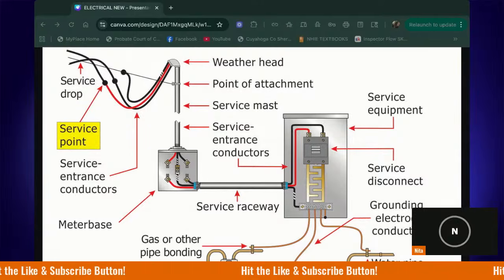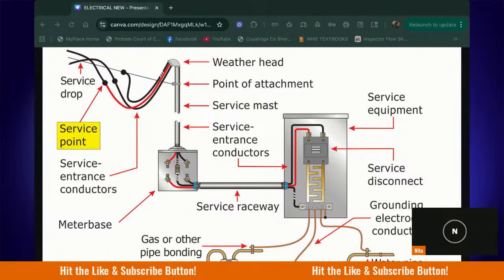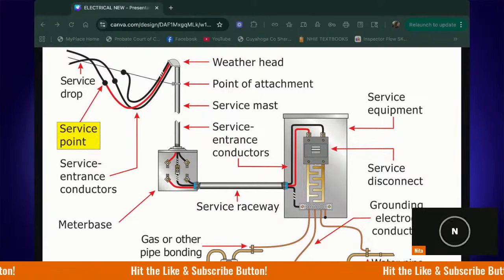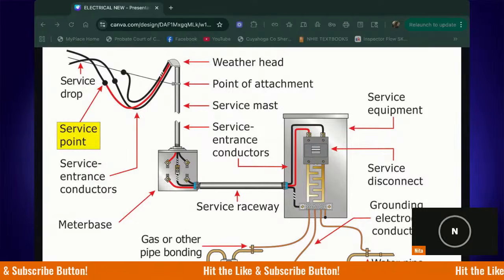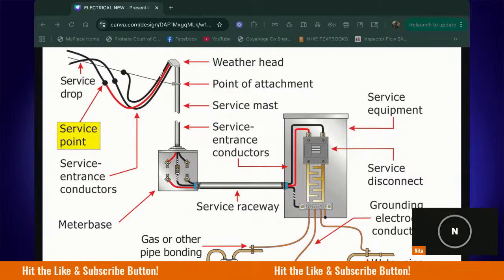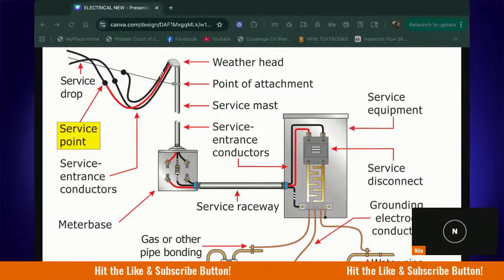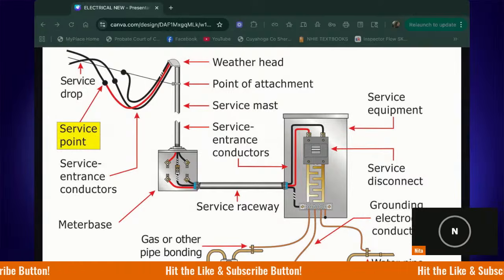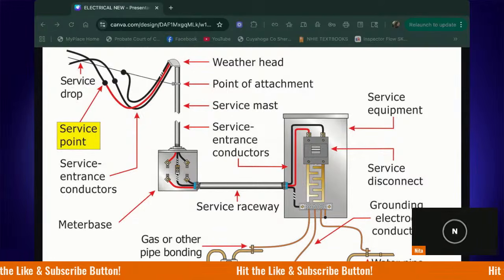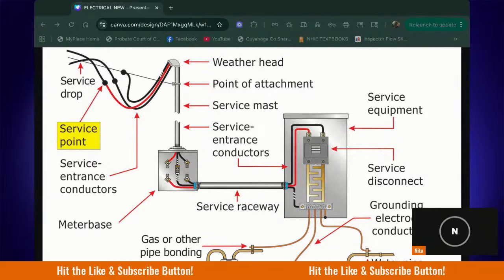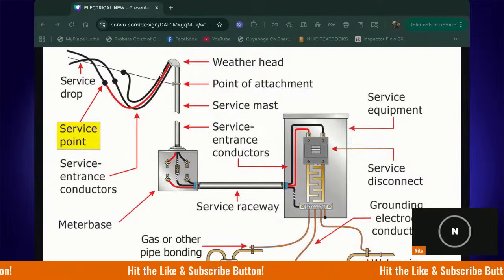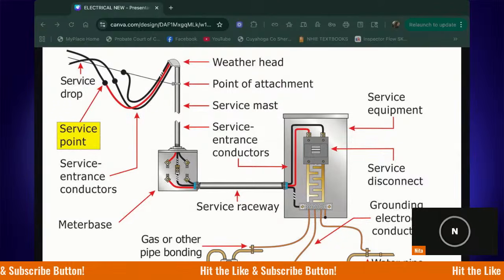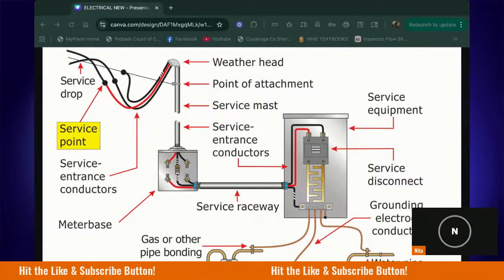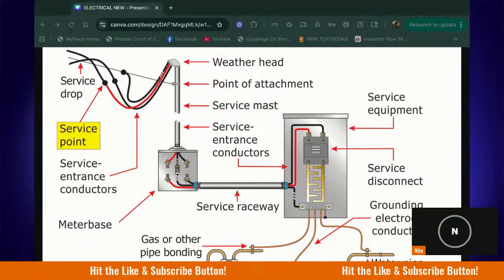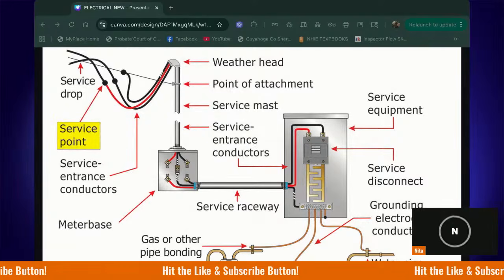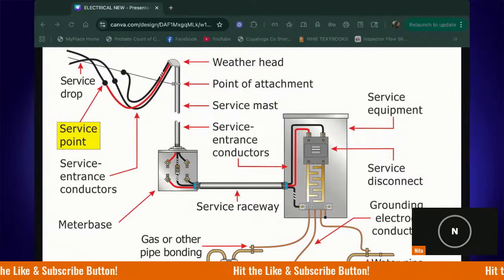Now, entering the house, the conductors that come into our home. A typical service entrance cable, the cable that's entering our home, will contain 2 hot conductors, each carrying how many volts? 120. That's correct. Each carrying 120 volts to neutral, and then one neutral conductor or the grounded conductor, which serves as the return path. Neutral is the return. Typically, these wires, and everything we'll learn, conductors are color coded. Hot conductors are typically either black or red, or they'll be black with a red stripe. Your neutral is either white or gray, and then your grounding wires are bare copper or green.